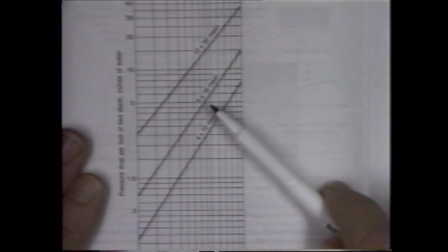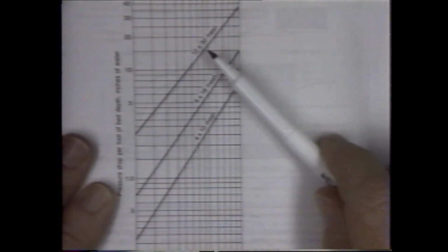This figure 12.6 is the one to use here because we happen to have a 4 by 10 mesh carbon, so it exactly matches up with this line. If you're given some other parameters, let's say a 6 by 10 mesh or a 4 by 16 mesh, you can see it's not going to fall on one of these lines, but you can use these to estimate. The larger the number of mesh in the screen, the smaller the particles of carbon. So as they pack in more tightly, you'll get greater pressure drop. That's why you see these lines going up as the numbers increase.